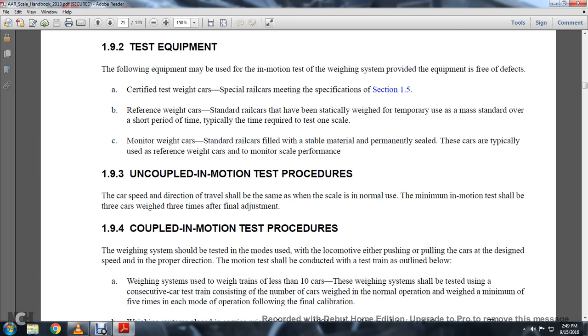1-9-3: Uncoupled In-Motion Testing Procedure. The car speed and direction of travel shall be the same as when the scale is normally used. The minimum in-motion test should be three cars weighed three times after final adjustment.